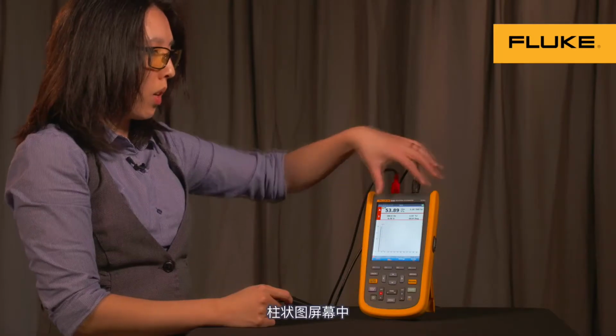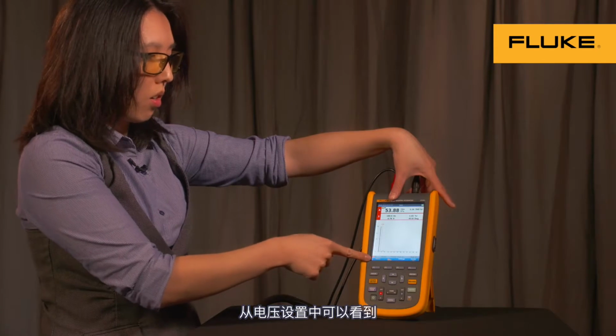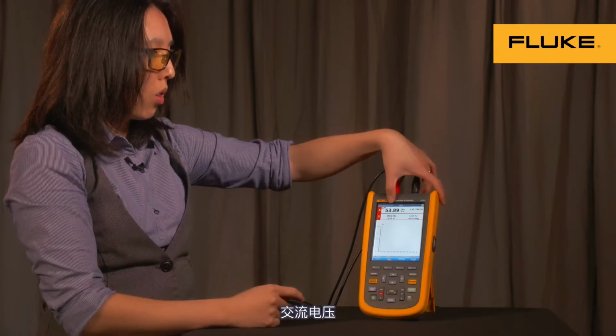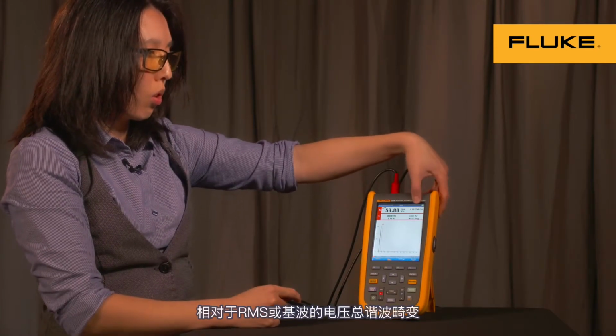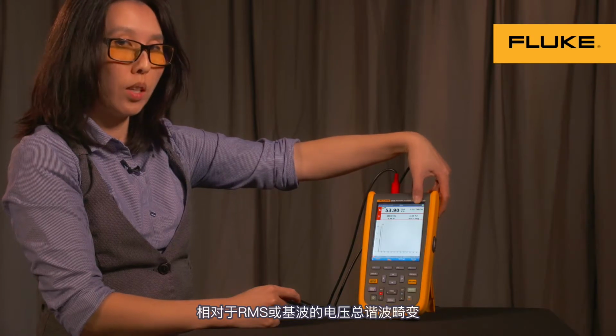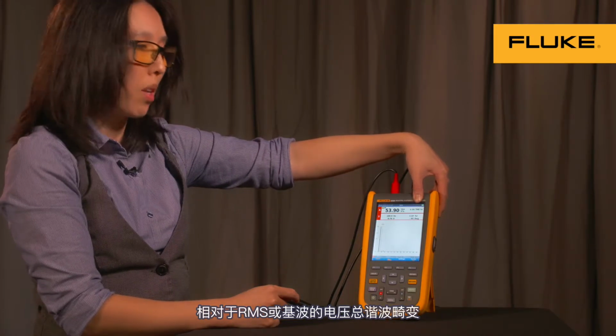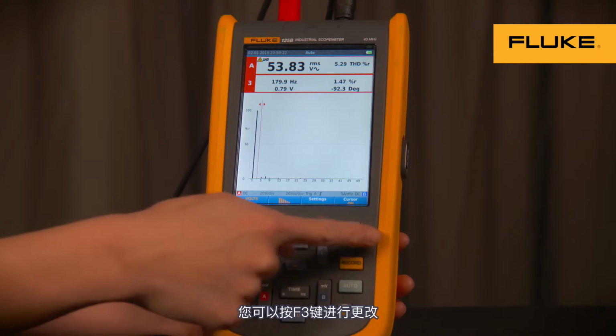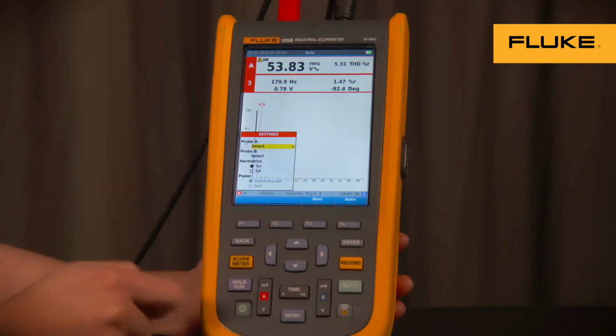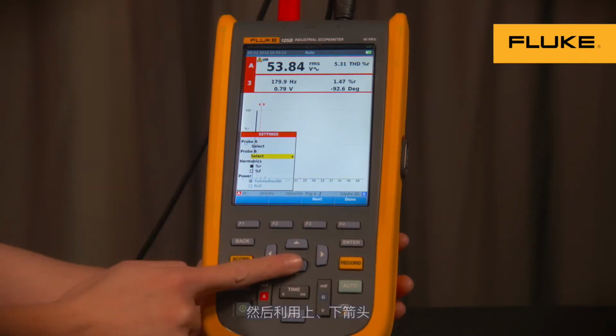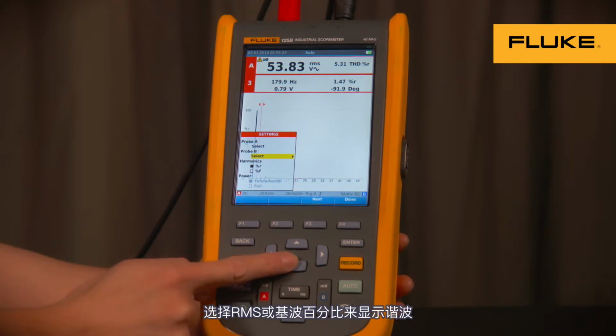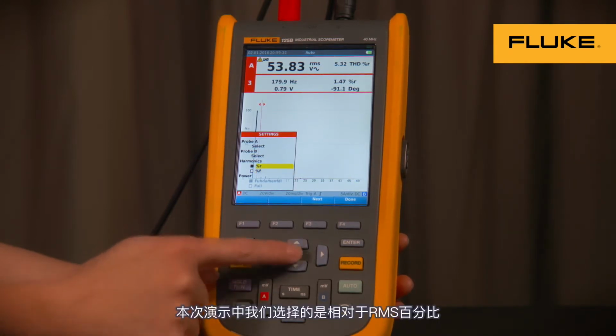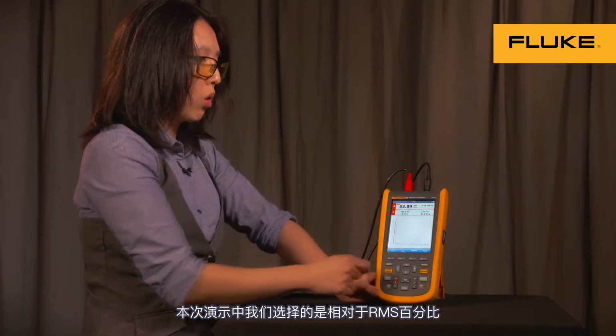In the histogram screen, you'll be able to see in the voltage setting your AC voltage, your total harmonic distortion relative to RMS or fundamental, which you can also change in settings by pressing F3 and using the up and down arrow to choose between relative to RMS or relative to fundamental. We'll leave it on relative to RMS for this demonstration.